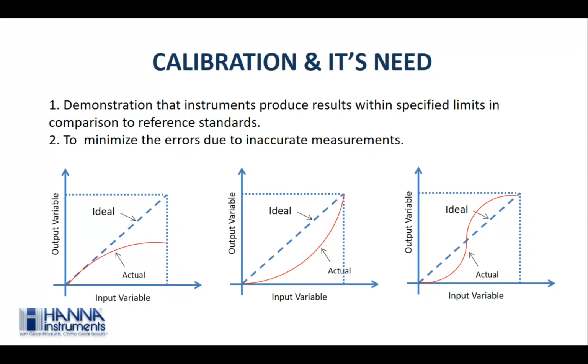Calibration tries to compensate for any deviation due to sample attack, storage processes, cleaning processes, or maintenance processes, any deviation from its ideal behavior. It teaches the instrument to yield accurate results when tested with unknown values. Calibration of an instrument is a very critical activity. Hence, it is done with a solution having known pH. All equipment should be calibrated with NIST traceable standards to guarantee the readings can be trusted.